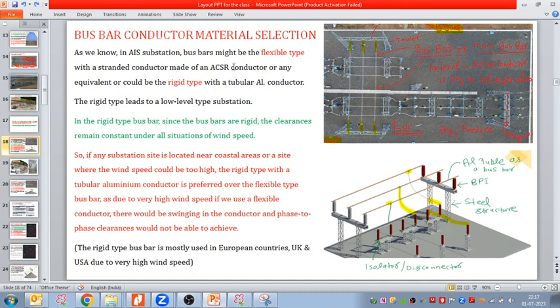In place of ACSR, we can go with the other option as well. In the SLD model, we have discussed the other options we generally follow, like triple AC, all aluminum alloy conductors, or any equivalent we can take to make the flexible type bus bar. Or the bus bar could be the rigid type. This rigid type is made with a tubular aluminum conductor.